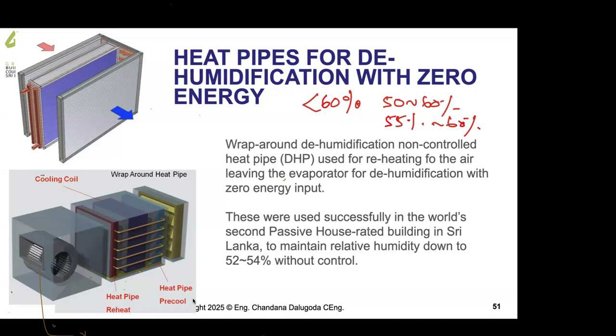So you let it drop down. The air conditioner cannot handle that. You need reheating. That is a psychrometric process, reheating. After cooling, you reheat, then relative humidity drops. Now, reheating is usually done by applying electric heaters. So there is a massive electric demand for heating. While cooling, heating is also required for dehumidification. But for green buildings, that is completely out.